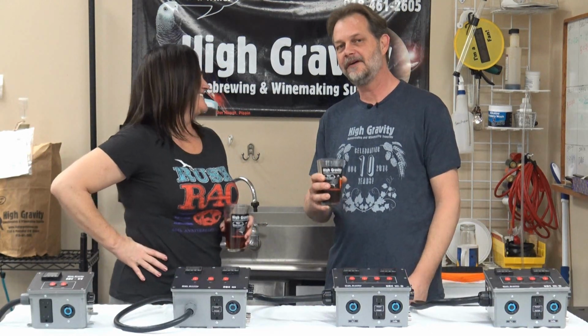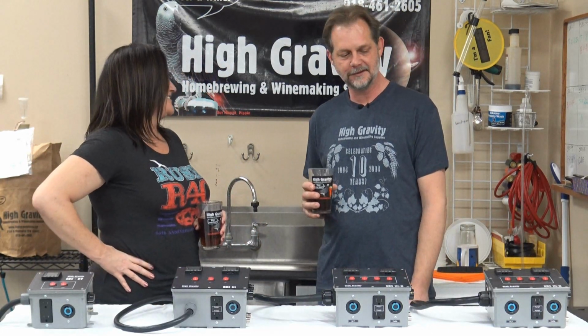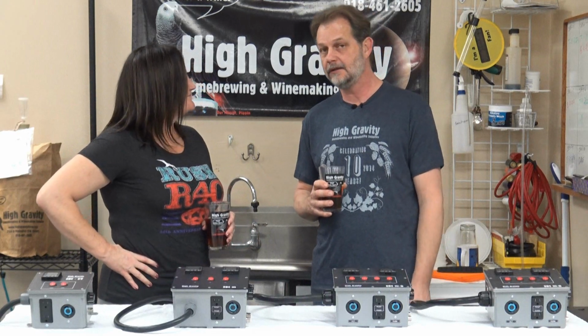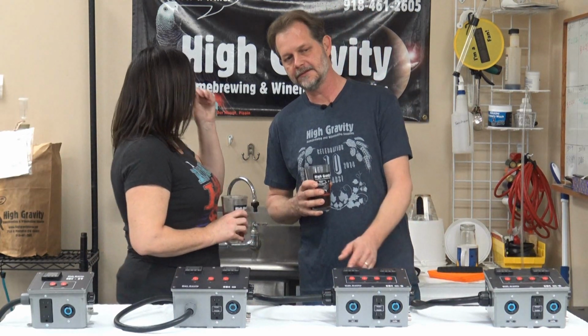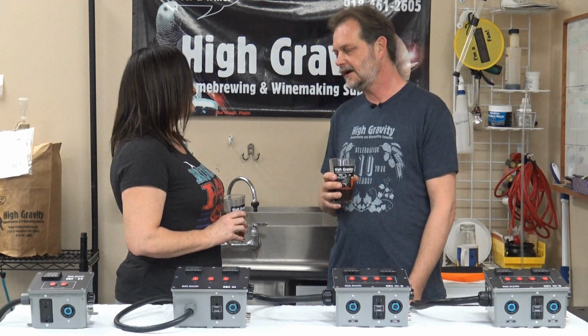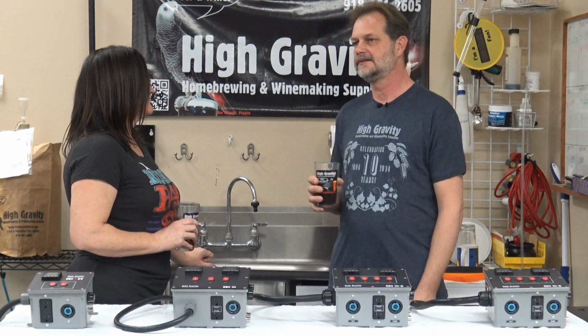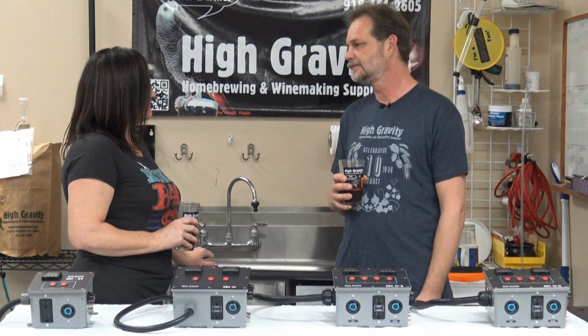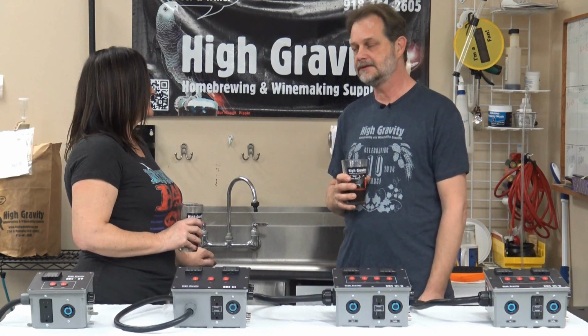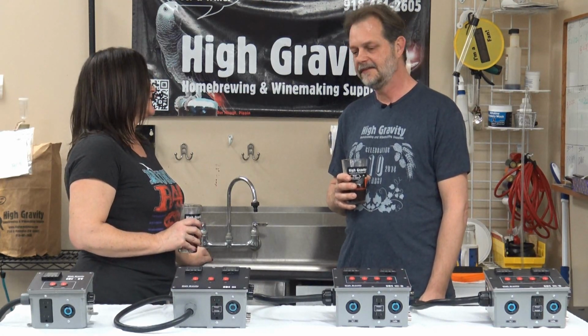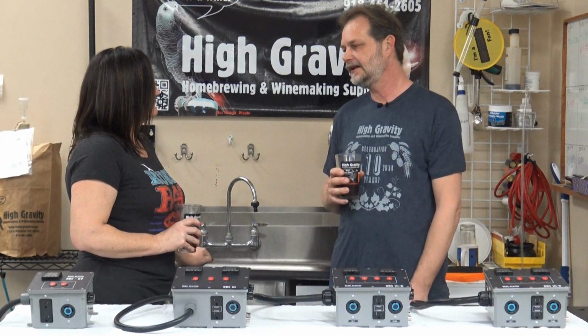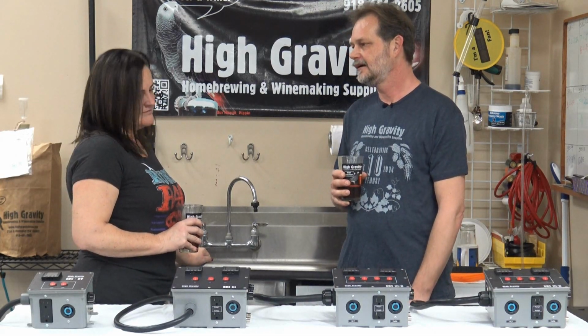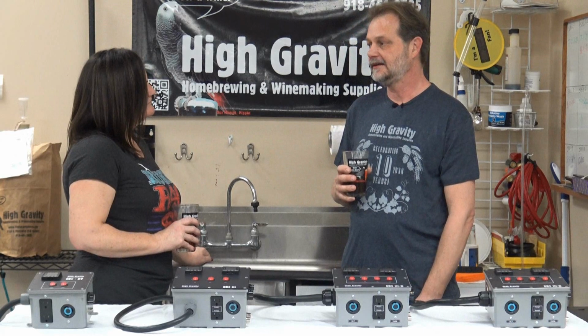What does 11.5 kilowatts do for a 1-barrel system? That's 2 5750-watt elements, and you can raise the temperature of 30 gallons about 200 degrees per hour. That's high performance. That's the same performance you get with 15 gallons.